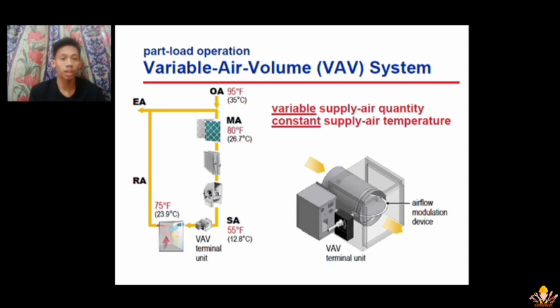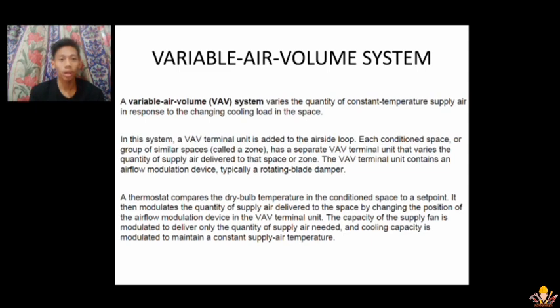Another part load operation is the variable air volume, or VAV, system. In this system, the supply air quantity is variable and the supply air temperature is constant. A variable air volume system varies the quantity of constant temperature supply air in response to the changing cooling load in the space. In this system, a VAV terminal unit is added to the airside loop. Each conditioned space or group of similar spaces, called a zone, has a separate VAV terminal unit that varies the quantity of supply air delivered to that space or zone.